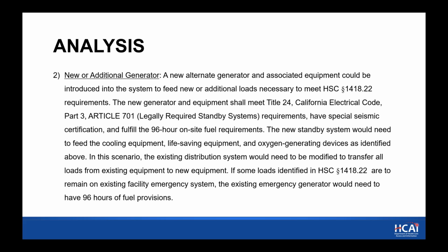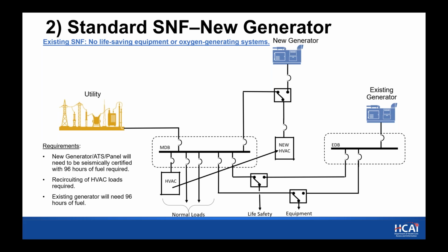So we'll go ahead and look at the 2 scenarios. It's probably the easiest way to explain it. So you'll see the original system as it's presented with an existing generator, 2 transfer switches, and assumed HVAC cooling equipment connected to normal. In this case, a new generator could be introduced at the site with a new transfer switch that feeds a new panel board. That panel board then could be used to feed the existing HVAC equipment used to maintain safe temperatures. So let's see, we'll look at this. Requirements: the new generator, ATS, and panel will need to be seismically certified, and you'll need to have 96 hours of fuel. Recircuiting of HVAC loads is required.